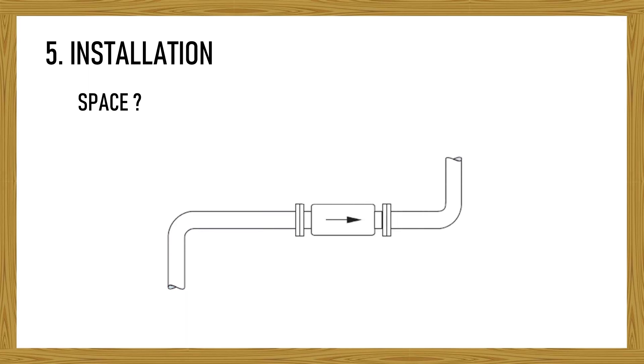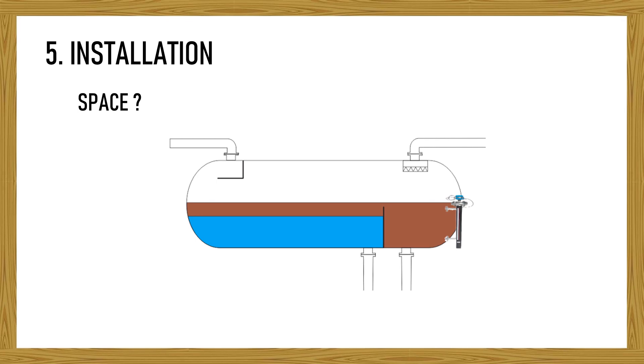Next is how the instrument will be installed. Space usually becomes an issue especially in an offshore platform where the space is limited. For example, some flow instruments require straight pipe run before and after the point of install. Space installation of level instrument which measuring low level sometimes becomes an issue when its bottom could contact with the structure surface.